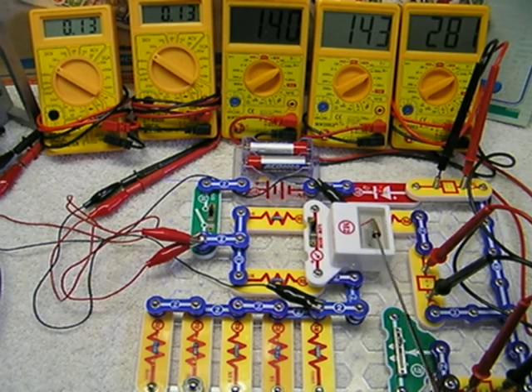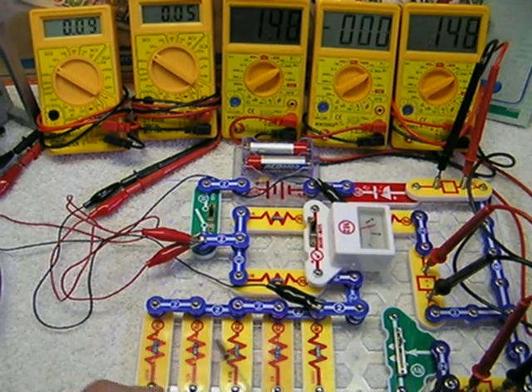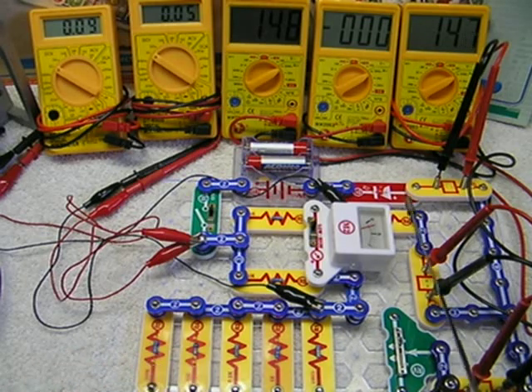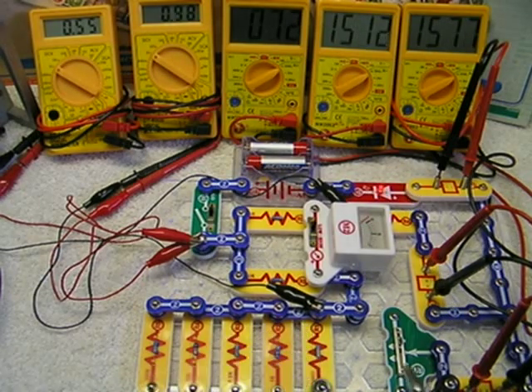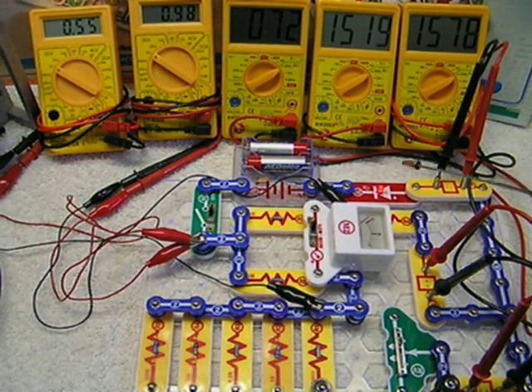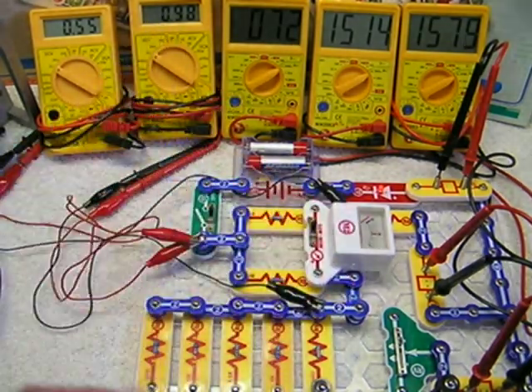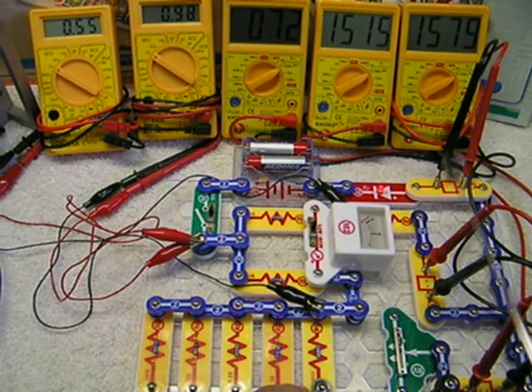If it's balanced, this meter will not change. That is, if I have the correct resistance selected down here to balance this unknown resistor up here, which would be my cable pair, let us say. So I'm going to select a resistor down here and look what happened. The meter went the wrong way. Now I know the circuit's on because the LED is on, but the meter went off the zero. So it's pretty obvious that this resistor is not adequate. It's not simulating or balancing this unknown resistor.